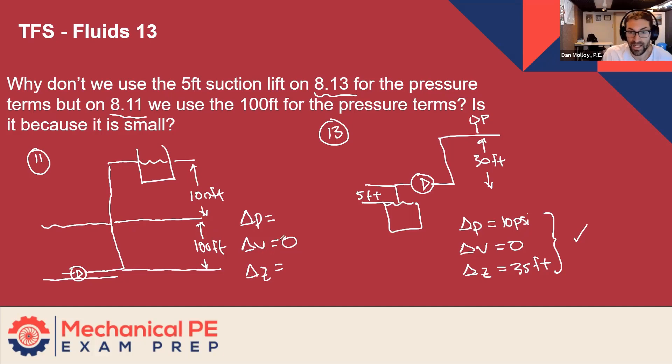And the answer to that kind of depends on where we establish our datum. So in the solution that I did in the video and in the book, I set the datum at the level of the pump. That just made the most sense to me. I think that's the most typical. We put it at the center line of the pump. And what that means is that the discharge head above the pump is the full 100 feet. So I define Z as 100.